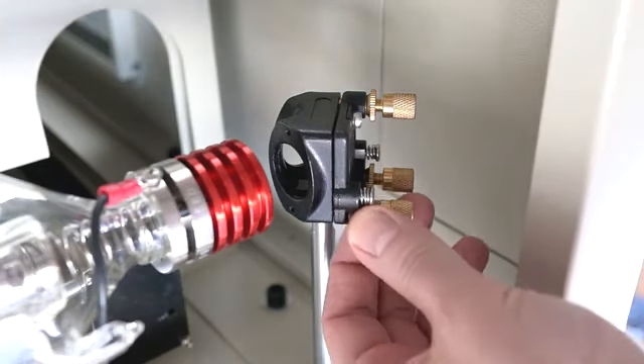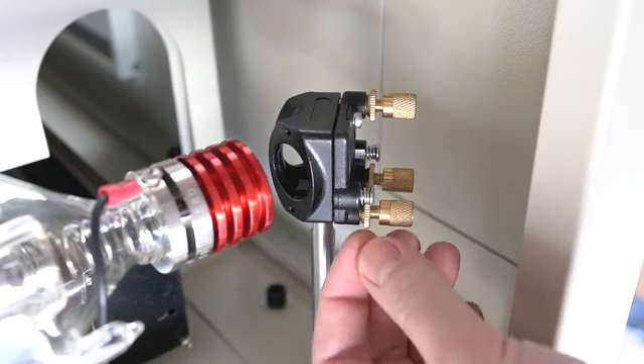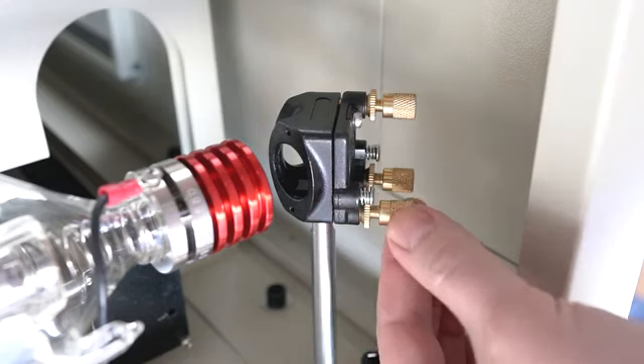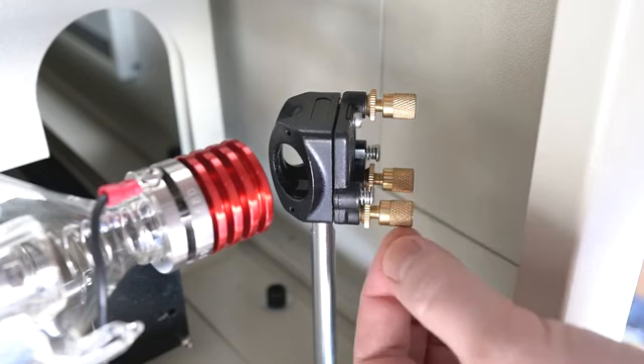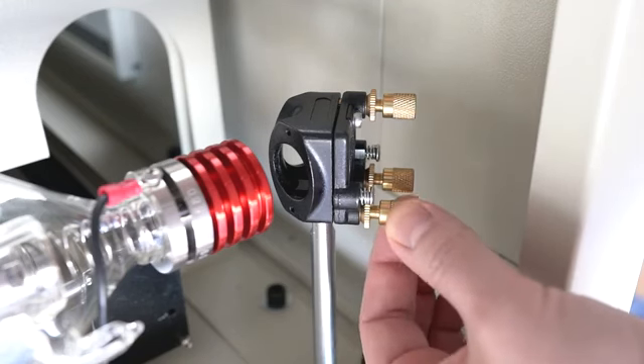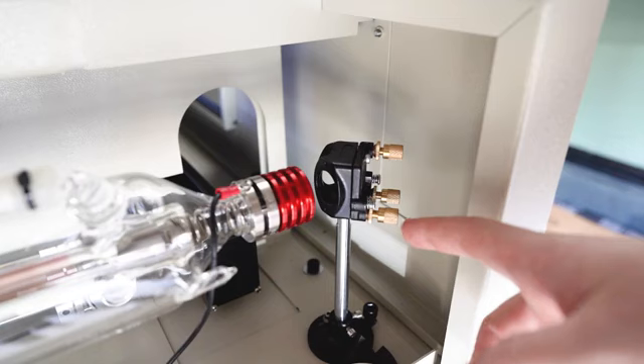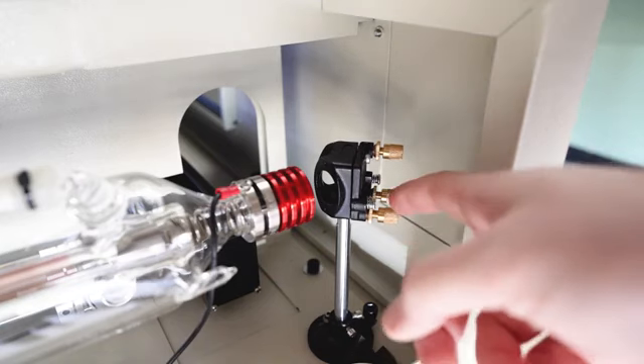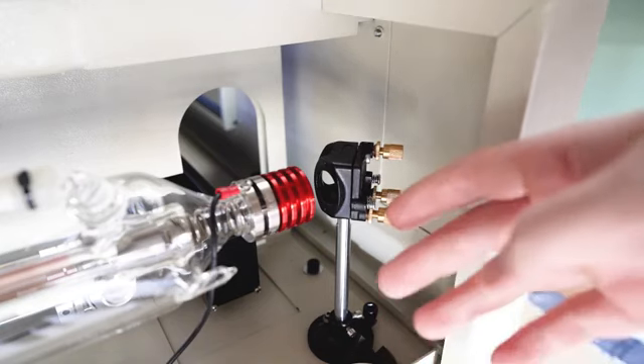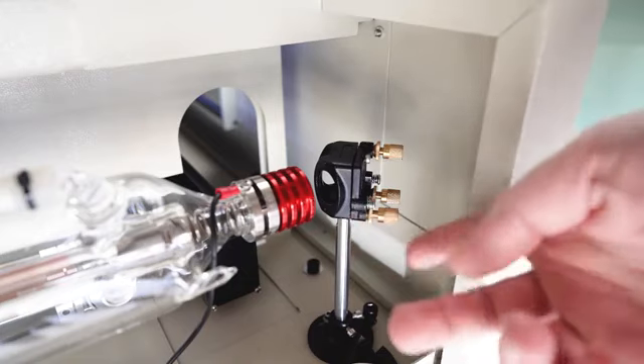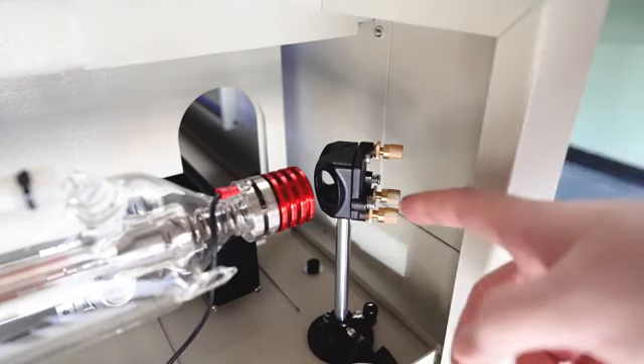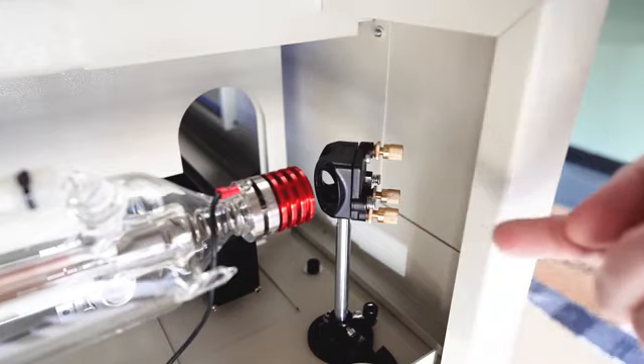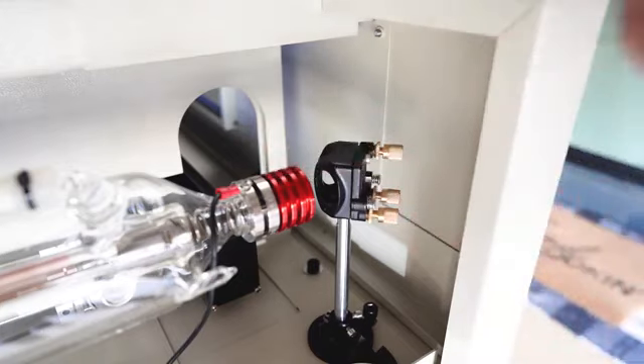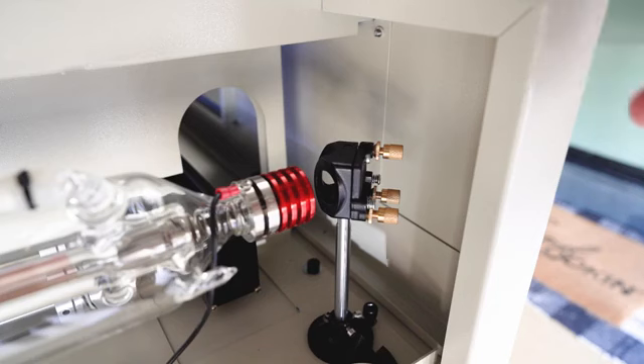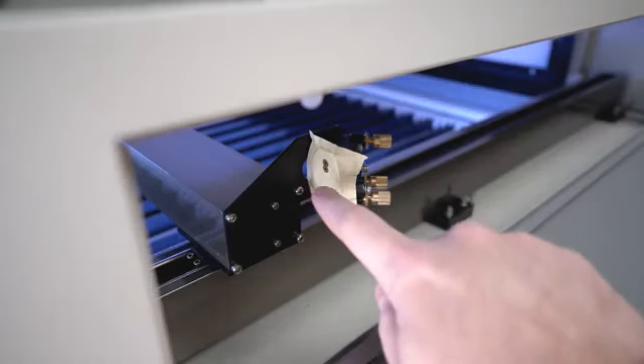The first thing you're gonna wanna do is to loosen up these locking screws, and then in small amounts change these dialing screws. So let's try that out. Okay, so it was actually counterintuitive. Loosening the screw here does not make the beam travel left. Loosening it makes the beam travel right. So tightening this screw makes the beam travel left, and doing so I've been able to get it centered on the x-axis. So let's take a look. So now it's centered left and right on the x-axis.